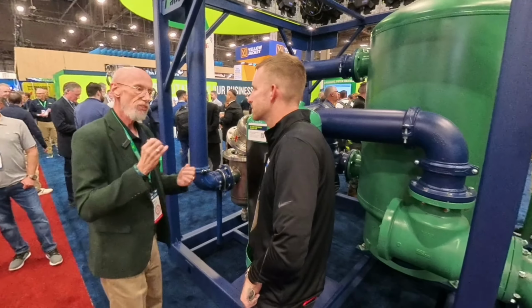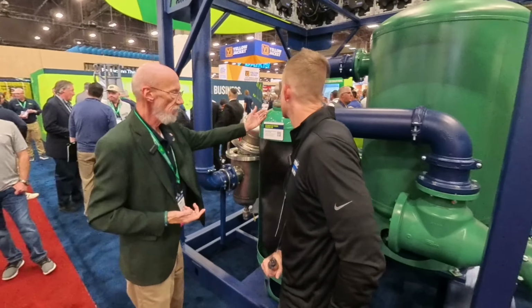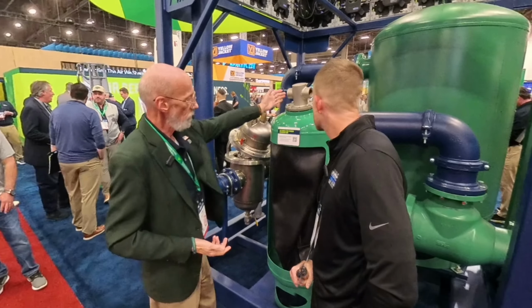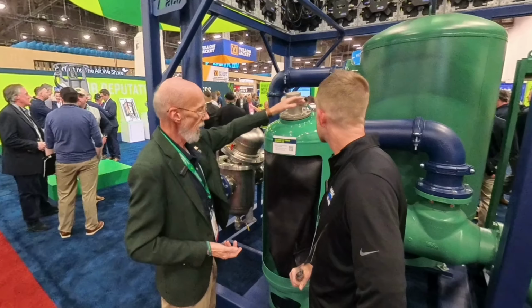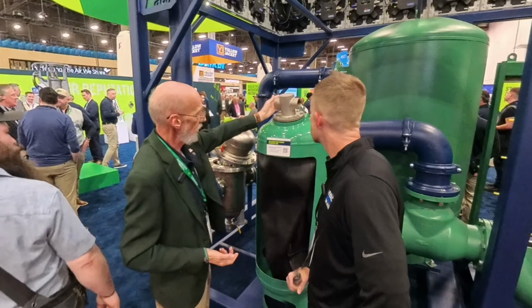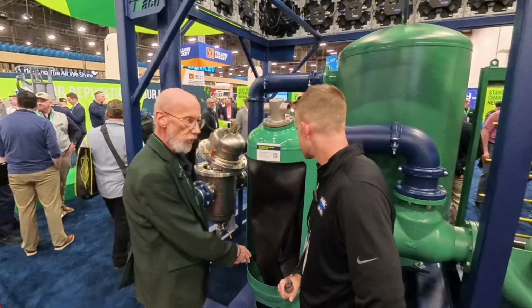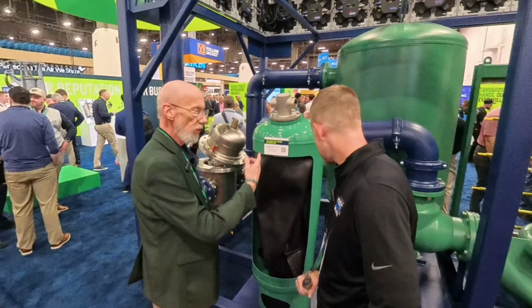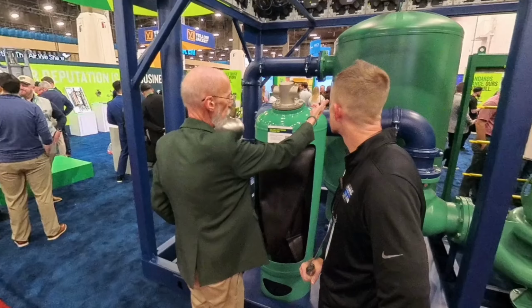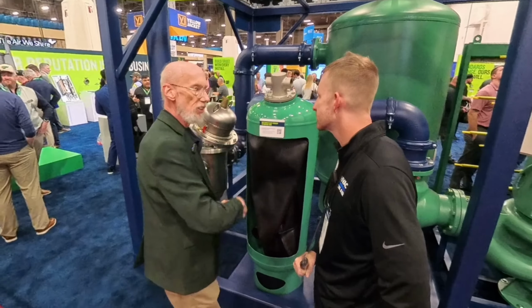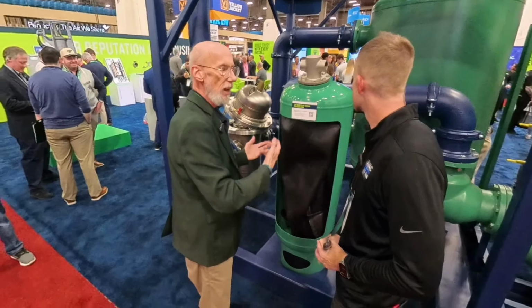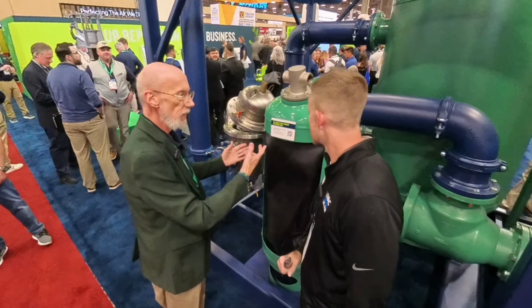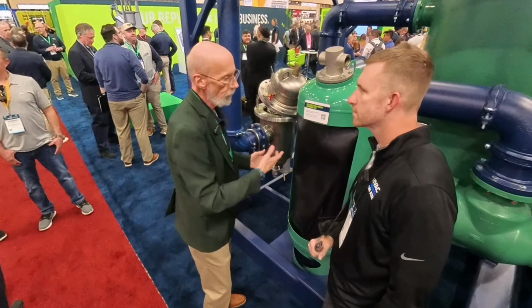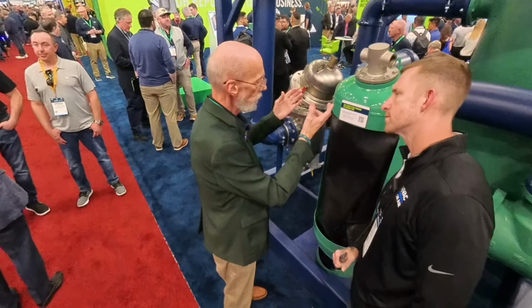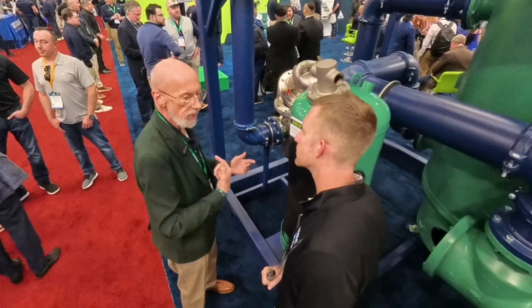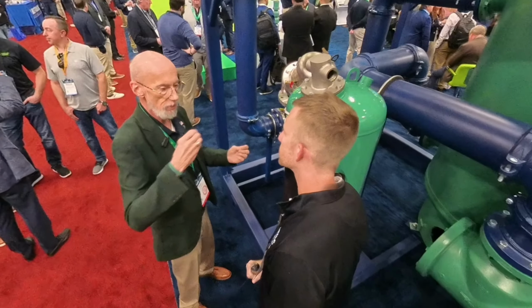Well, what we've done is we've solved that problem. We've built our CAF series flow-through expansion tank. It is a multi-port design, so it has an inlet port and an outlet port. Cold water comes into the tank. There's a dip tube that goes down through the tank, so the water's always going through the tank and coming back out the outlet port, so that we're always changing the water over in the tank. We never, ever have a dead leg, so the tank doesn't become a harbor of bacteria. We know through computational fluid dynamics that we're always going to have the right flow rate through the tank. We're always going to keep the water stirred up from minimum flow all the way up to design maximum flow.